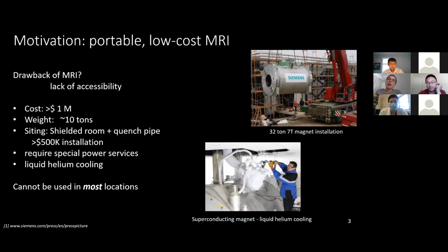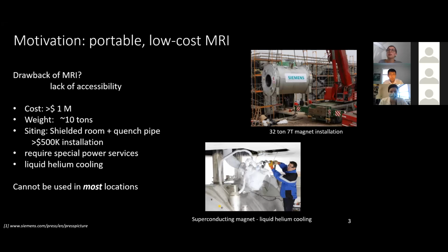So the biggest drawback of traditional MRI is the lack of accessibility. Conventional MRI scanners cost millions of dollars and weigh tens of tons. Siting and installation is very difficult and expensive because it requires the construction of a special shielded room and the installation of a quench pipe for the superconducting magnet, so installation can cost $500,000 on its own. It also requires the installation of special power services, and liquid helium cooling is needed for the superconducting magnet. This means that MRI really cannot be used in most locations.